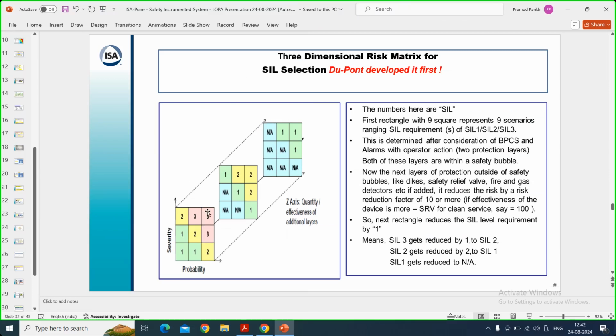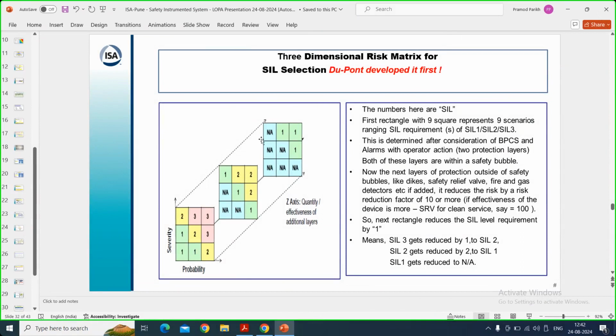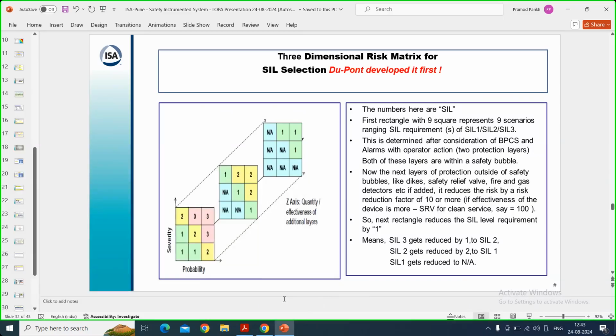So this is a risk matrix. These are the SILs. SIL 3 gets reduced to SIL 2. SIL 2 gets reduced to SIL 1. It all depends upon that. I want to include computer audio when I'm explaining this. Okay. So you can reduce the SIL by adding additional protection layers. The risk matrix, as I mentioned, is not very accurate. So if you want an accurate assessment, then you have to go for LOPA only.